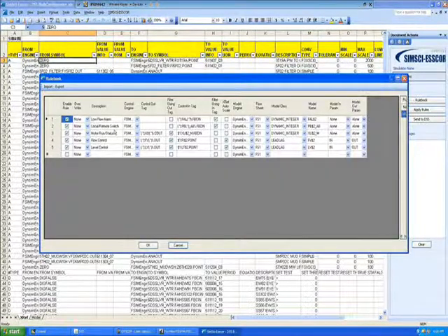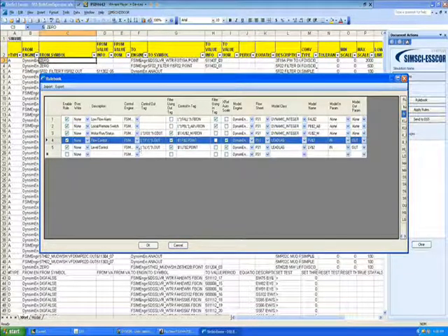The rulebook searches the I/O tags for patterns and builds a tieback model based on the pattern that's found. For instance, the tag FY denotes a flow control valve and FT denotes a flow transmitter. From this we know we can build a flow tieback model.